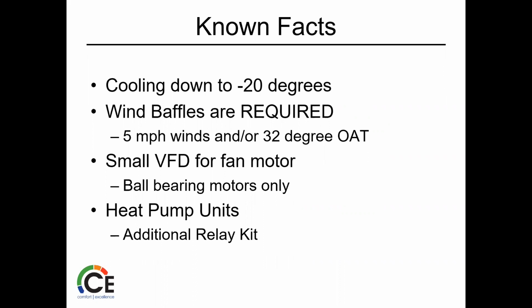And if you're using this one, it doesn't matter what your application is at this point. Put some wind baffles on it. 5 mile per hour winds and or 32-degree outdoor ambient temperature. So again, it's going to look at both, and it's going to help you if we got some wind and we're cooling things off. Now we're going to do both. That controller is basically a small VFD for the fan motor. Has to be a ball bearing motor. And then if it's a heat pump, we need that additional relay.